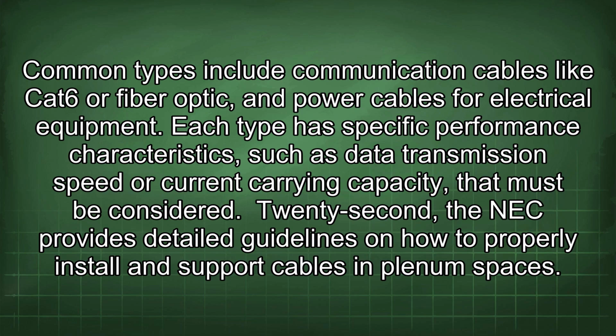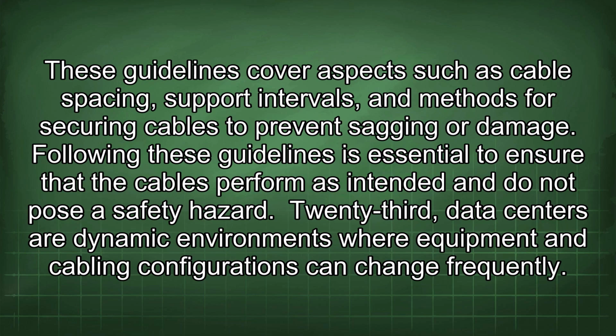22nd, the NEC provides detailed guidelines on how to properly install and support cables in Plenum spaces. These guidelines cover aspects such as cable spacing, support intervals, and methods for securing cables to prevent sagging or damage. Following these guidelines is essential to ensure that the cables perform as intended and do not pose a safety hazard.